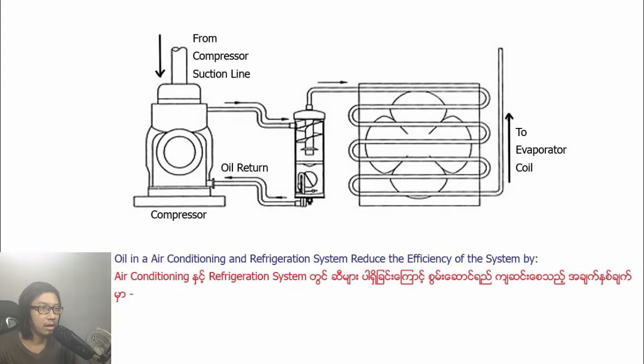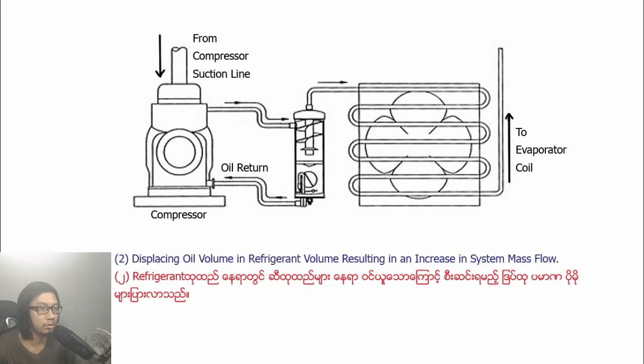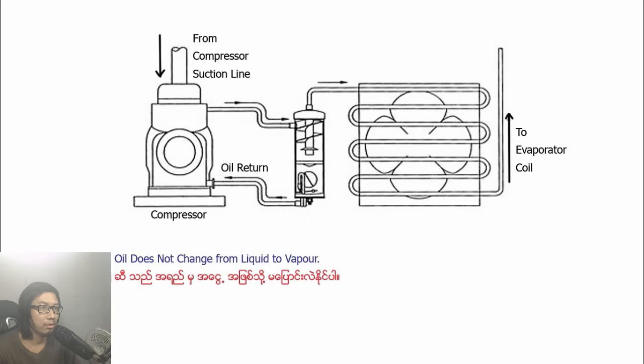Oil in the air conditioning and refrigeration system reduces the efficiency of the system by: 1. Reduction in heat transfer due to oil coating of the condenser and evaporator. 2. Displacing oil volume and refrigerant volume, resulting in an increase in system mass flow. Oil does not change from liquid to vapor.